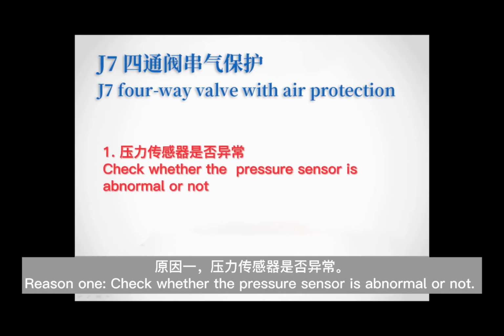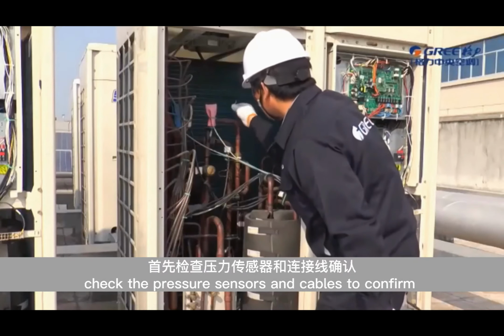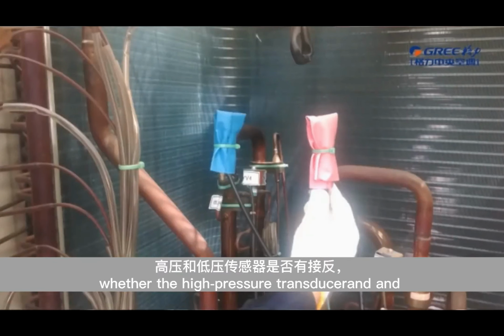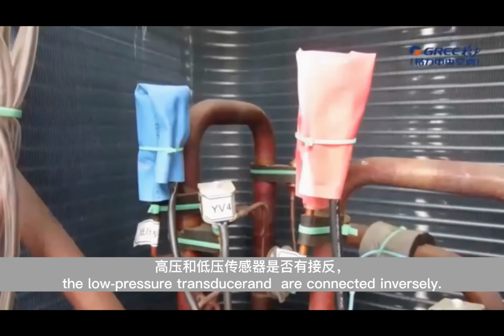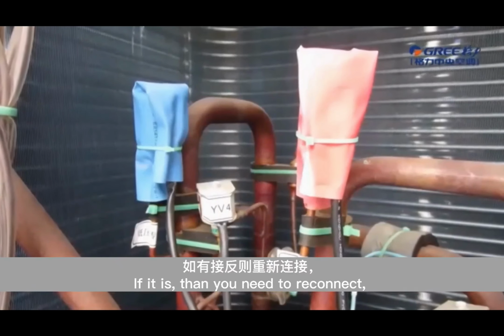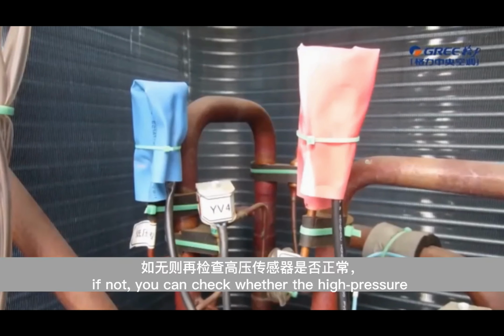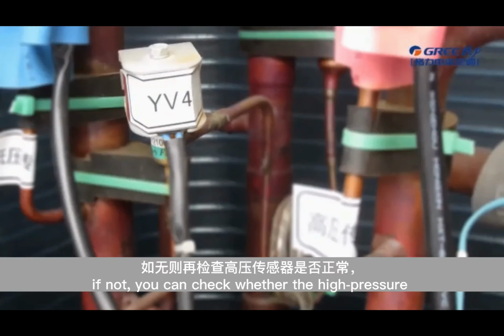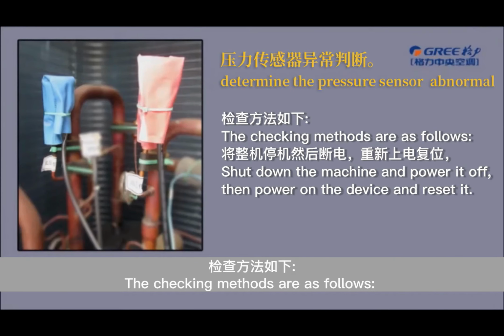Reason 1. Check whether the pressure sensor is abnormal or not. Check the pressure sensors and cables to confirm whether the high pressure transducer and the low pressure transducer are connected inversely. If they are, then you need to reconnect. If not, you can check whether the high pressure transducer is normal or not. The checking methods are as follows.